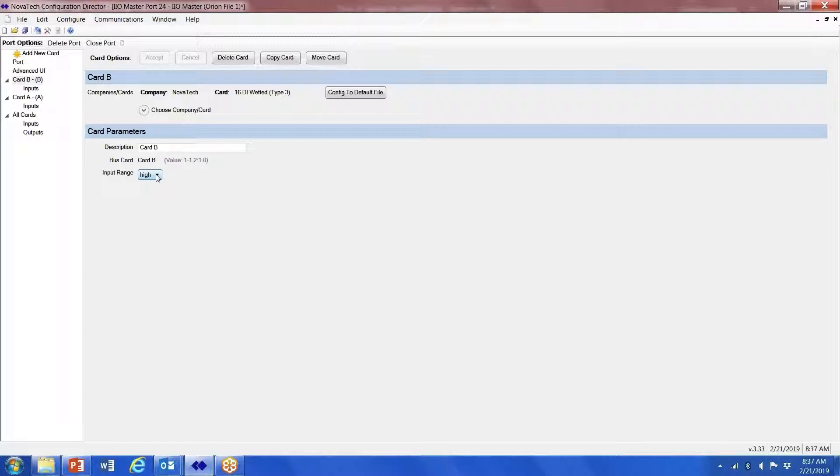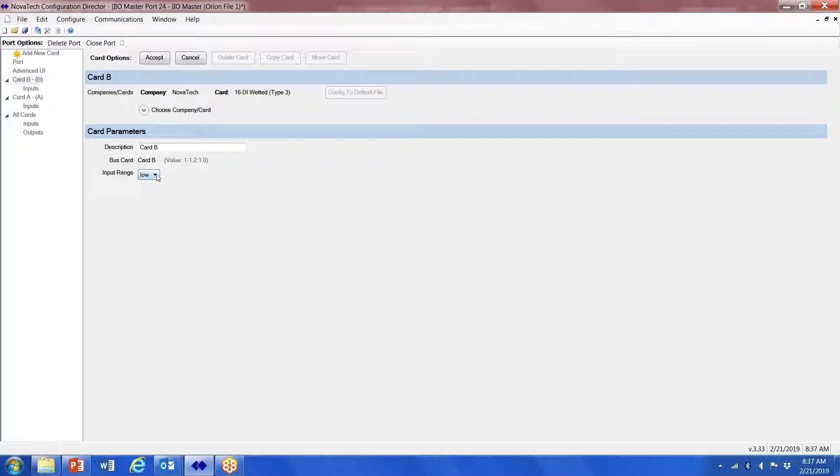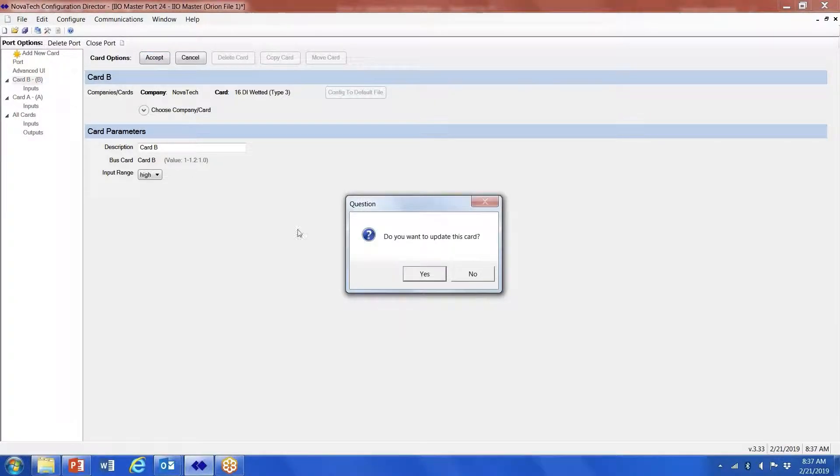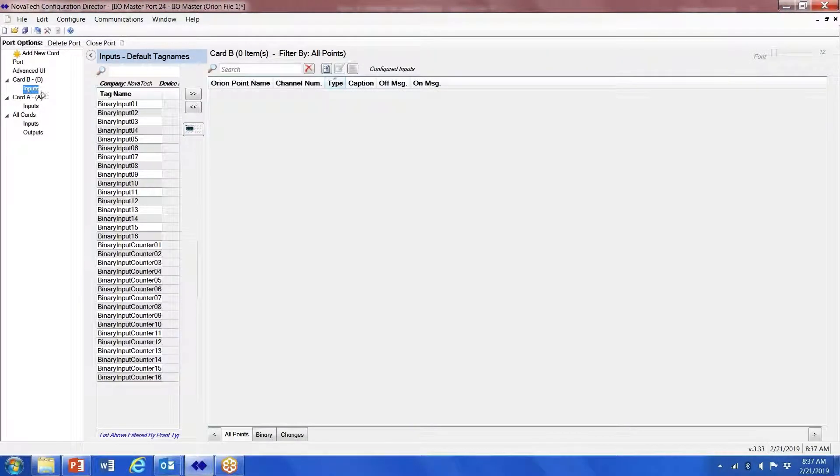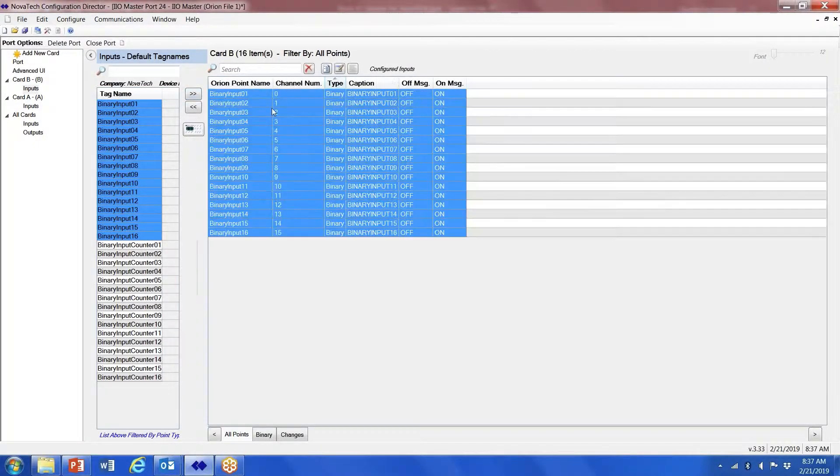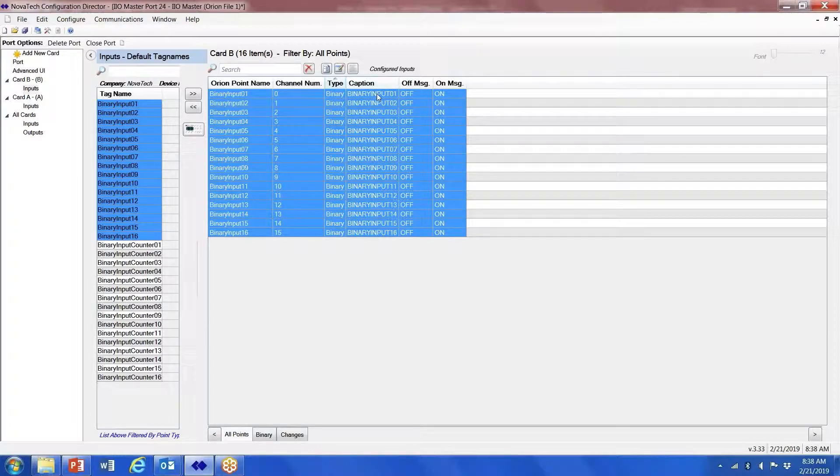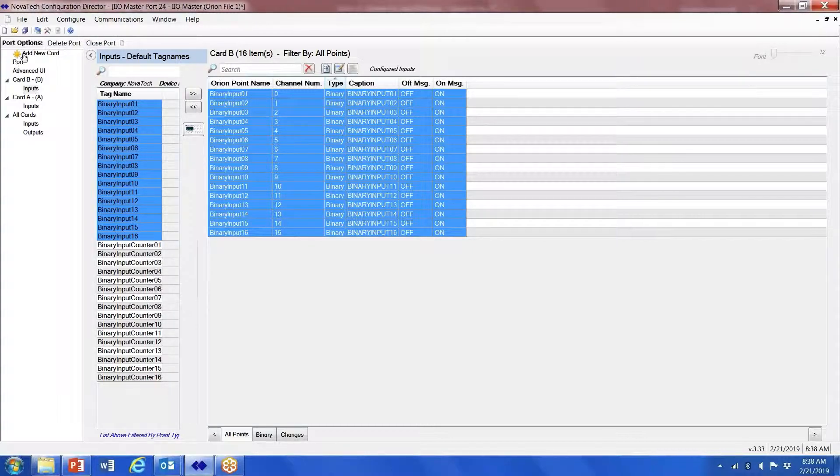On the wetted card we have two options for wetting voltage. The card actually has a 24 volt and a 48 volt DC power supply built onto it. If you select high, you're using the 48; if you select low, you're using the 24 volts. Once I've done that, click on accept and follow the same routine. Click on inputs, map over the inputs, and change my caption that I want displayed on the advanced display when I push the button.